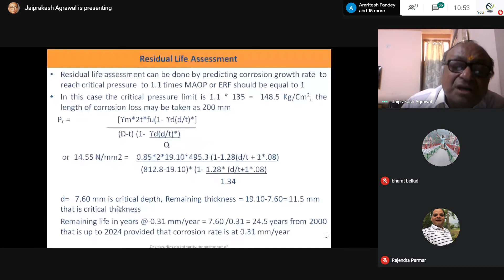So if it is 19, then 20, 21, 22, 23, 24. 5 years more life is there. So you have to take preventive as well as corrective actions in 2.5 years, half of the 5 years. Before the next 5 years, you do the intelligent pigging for that. Before that, you have to take action to increase the thickness to the original thickness or more than your critical depth. So this is how you calculate the residual life assessment and your critical pressure. If you have any question in this, if you have understood, then you tell me. Otherwise, next case study I will ask you to do.